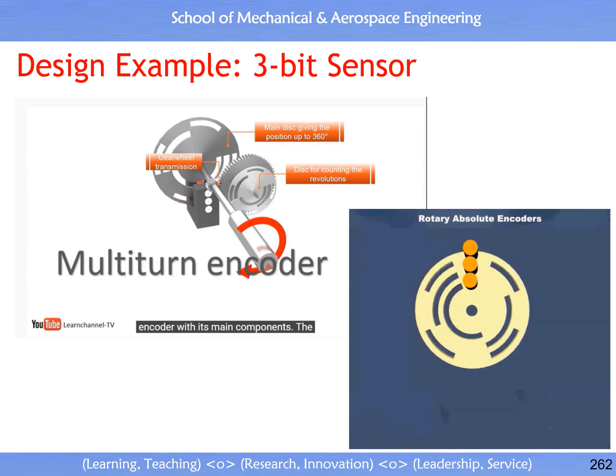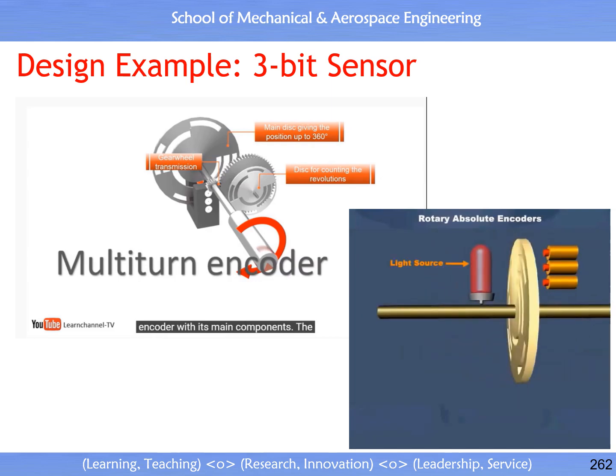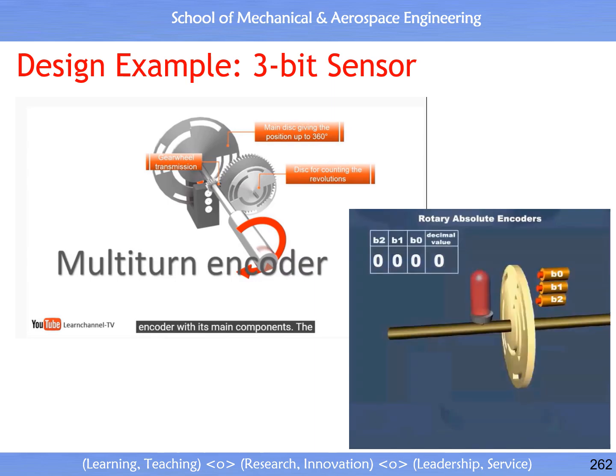Rotary absolute encoders consist of a translucent disc with a binary pattern etched on it. The pattern consists of a series of opaque and transparent slots. The slots are arranged in a concentric circular fashion, and the number of slot sets is the same as the number of photocells used in the encoder. A light source is located on one side of the strip, while photocell detectors are placed on the other side. The rotary absolute encoder shown here has 3 sets of slots and hence uses 3 photocells.